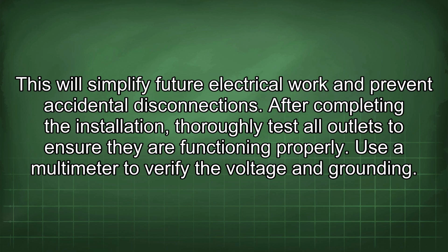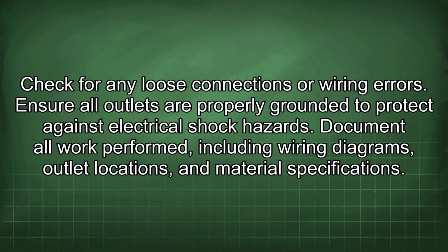After completing the installation, thoroughly test all outlets to ensure they are functioning properly. Use a multimeter to verify the voltage and grounding. Check for any loose connections or wiring errors. Ensure all outlets are properly grounded to protect against electrical shock hazards.